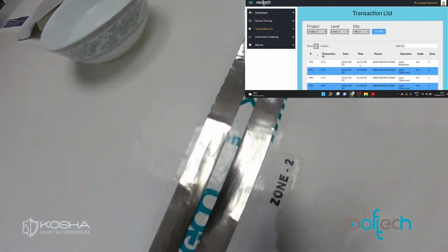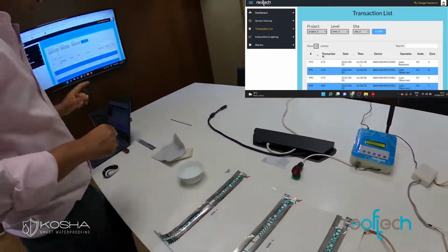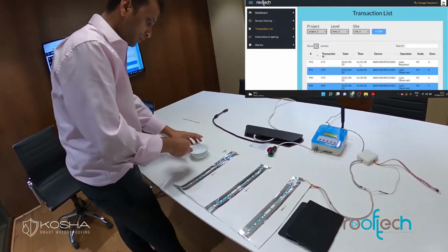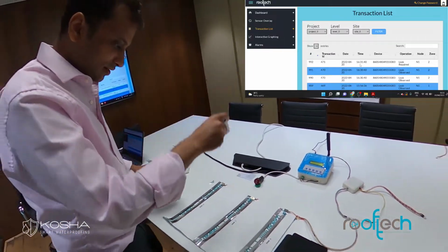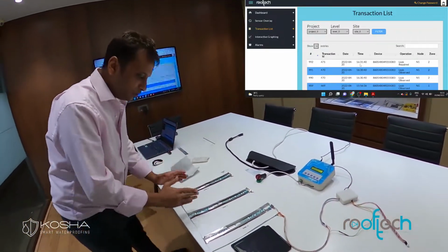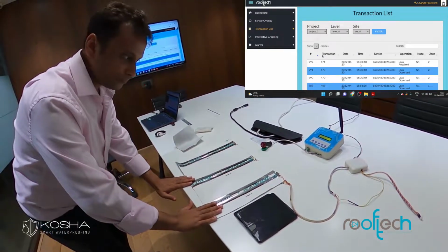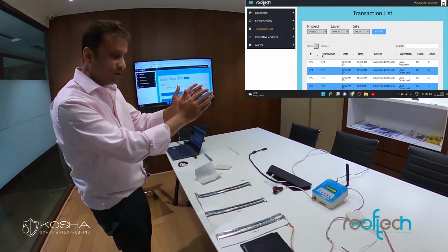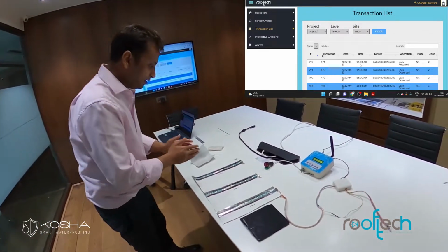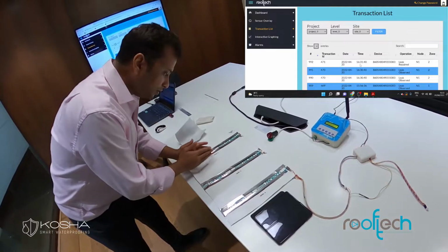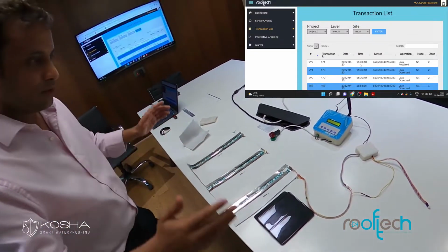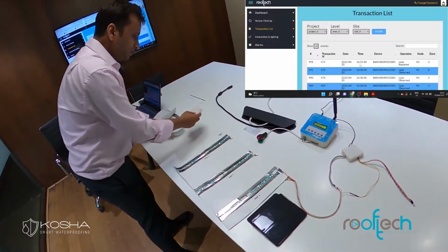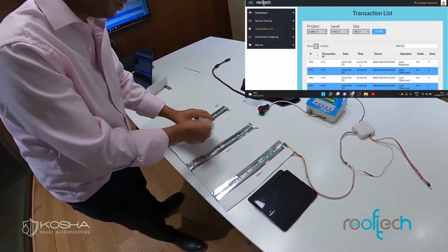Similarly, the system is smart enough that if something started leaking... the closer the distance between two sensor strips, the more accurately you can identify which location started leaking. The maximum distance between the tapes would define the accuracy, so you'll be able to pinpoint the location.